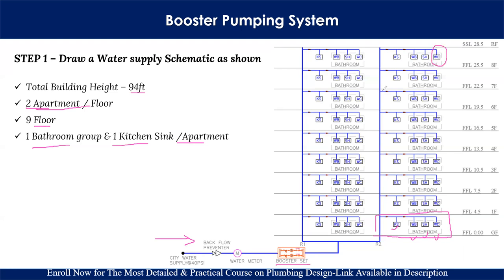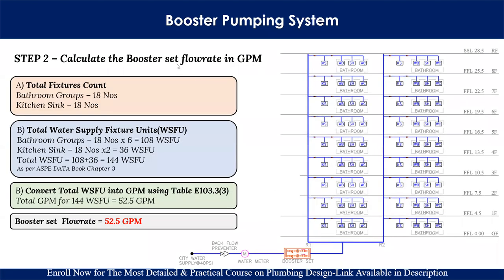Step two is to calculate the booster set flow rate — how much water flow rate is required. The first part is to calculate the total fixture count. There are nine floors, each with two apartments. One apartment has one bathroom group and one kitchen sink. Total number of bathroom groups: 9 × 2 = 18. Total number of kitchen sinks for the complete building: 18. Now we calculate the total WSFU — water supply fixture units.